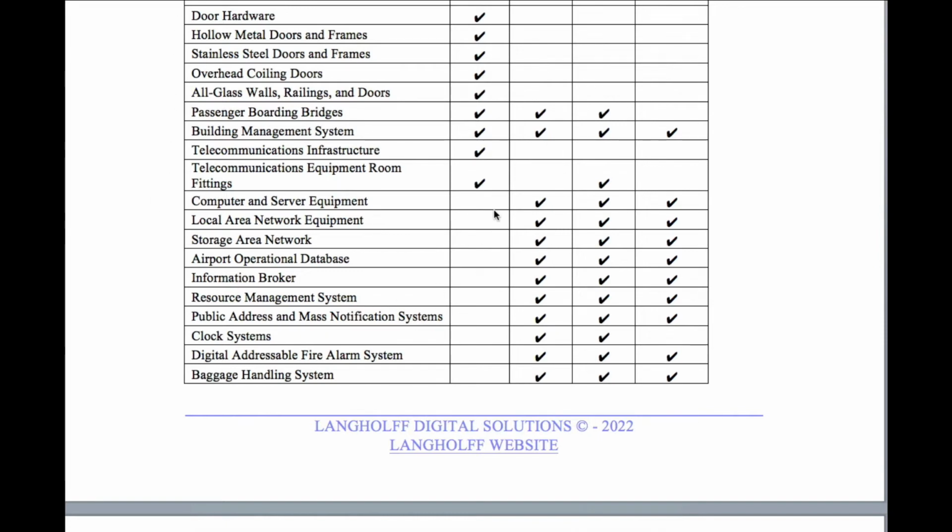Now, that could be included in the local area network, but for clarity's sake, the reason I left it out is because most people forget that they need a Wi-Fi connection to the access control system. These were some, not necessarily errors, but omissions from specifications that I was previously involved in where we were implementing the system. So this Wi-Fi connection became an area of dispute.